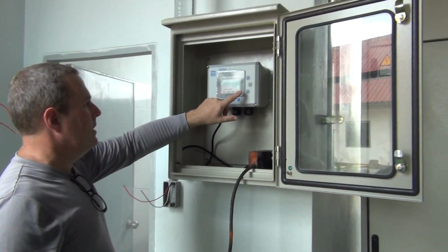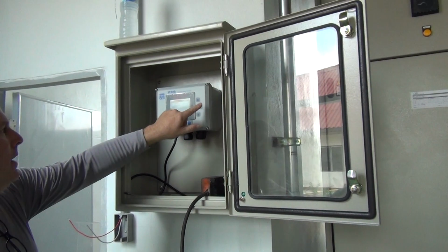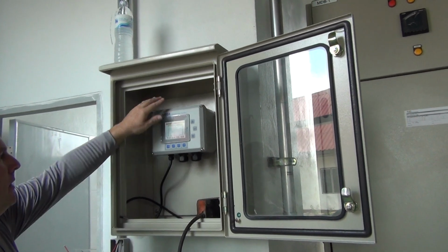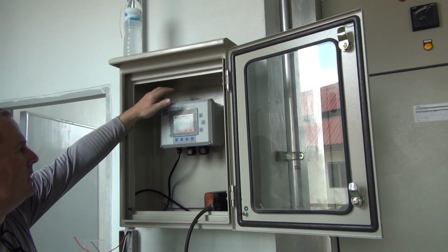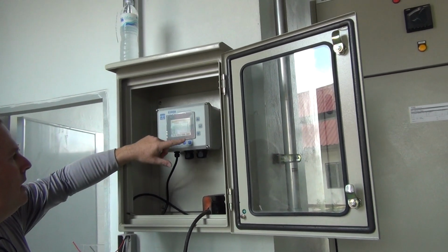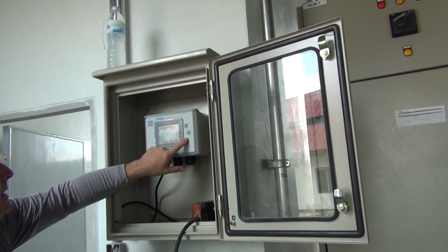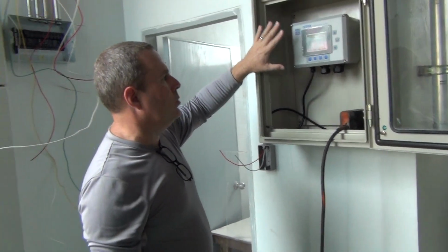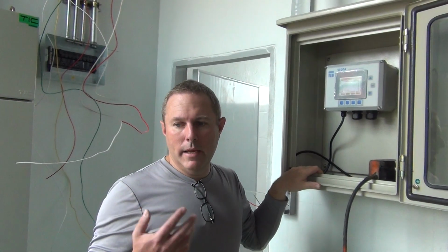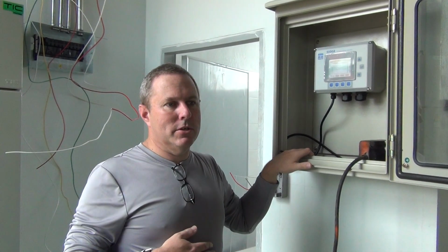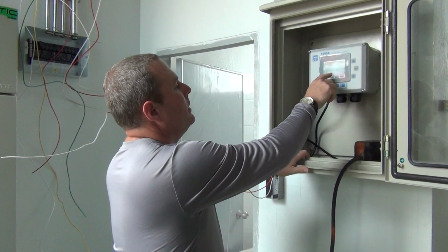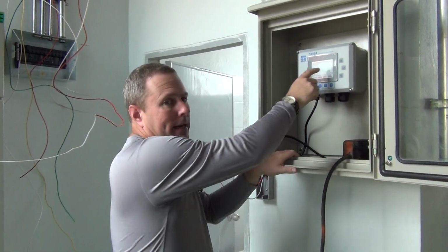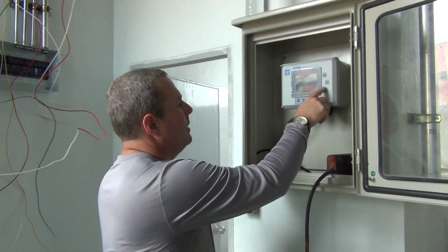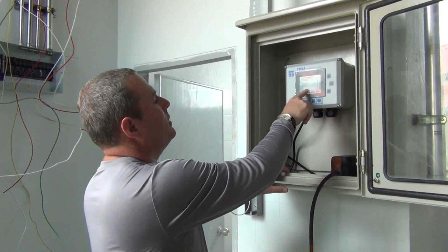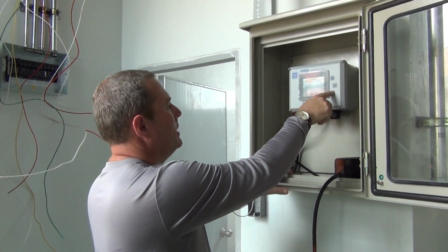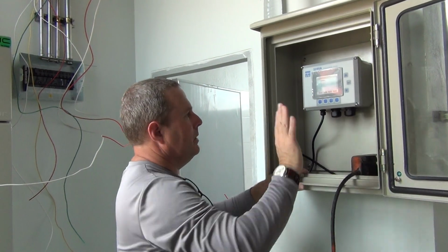Okay? So the next version displays the software version on the unit, and this version, the display board, which is the front module, is version 2. The control board is version 2, and it says the software was compiled May 20th of 2015. You normally would not need to worry about this. This is used only for diagnostics if you're on the phone with a technician. Then it tells you that the unit temperature is 47.3 inside, so it's quite toasty inside. Okay. And the power, it's at 12.07 volts. There's no battery hooked up and what the model number is. And that completes the system menu.